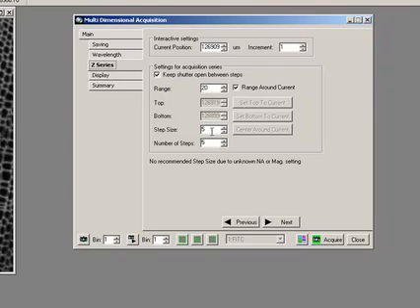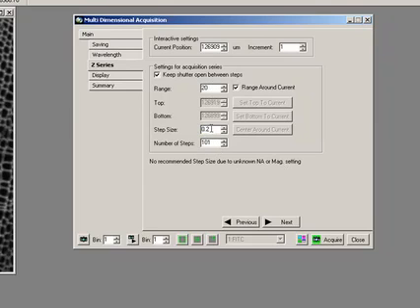And it tells you my step size is 5 microns and it wants to take 5 steps. So normally we would sort of slice it around the wavelength of light, people trying to be completely accurate for deconvolution, about 0.2 is a normal number. So that will calculate that I need to do 101 steps to do my 20 microns. So let's just do 0.5, so I'm being a little bit inaccurate. That's got 41.